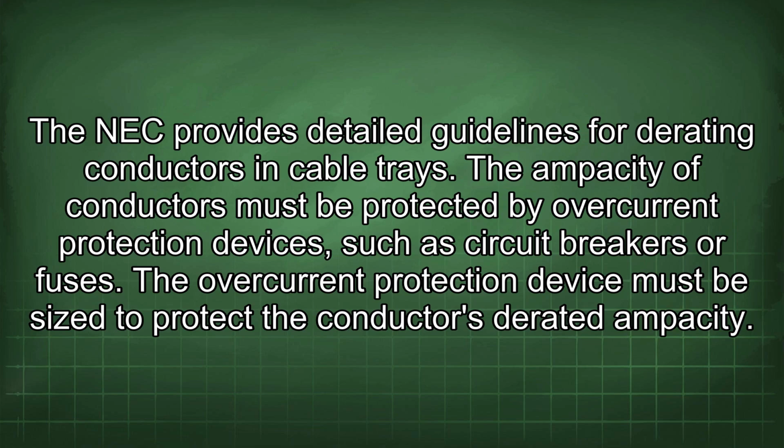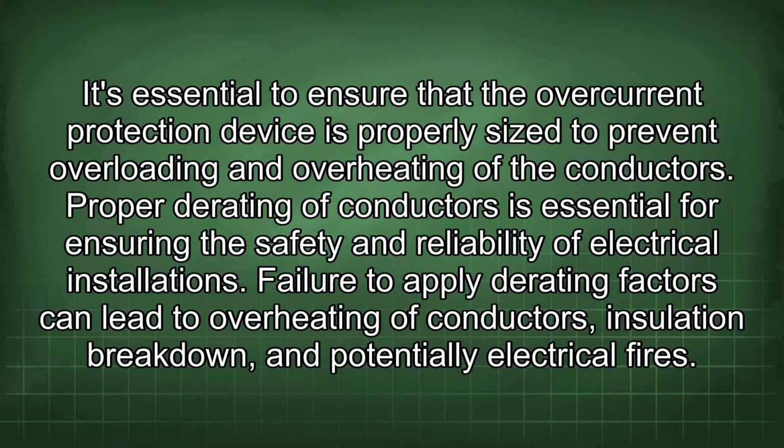The ampacity of conductors must be protected by overcurrent protection devices, such as circuit breakers or fuses. The overcurrent protection device must be sized to protect the conductor's derated ampacity. It's essential to ensure that the overcurrent protection device is properly sized to prevent overloading and overheating of the conductors.